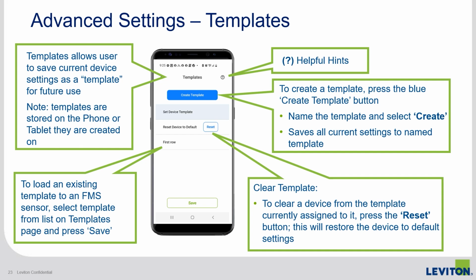For example, if you're doing multiple rooms in a large building that requires the same setting, you can save a room as a template and simply upload that template for the next room rather than going through each setting and making changes. After doing the first room, you can create a new template by clicking on the Create Template button and giving it a name. For the next room, go back to the same page and you'll see the template you created. Click on the template and press Save and the settings will be uploaded.